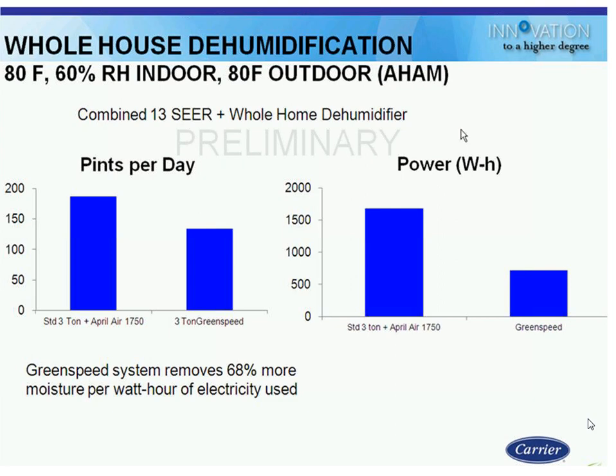This also gives you an idea on how much of a dehumidifier this guy can be. This is a 3-ton unit. On the left side, it's how much moisture is being removed. That first blue bar, where it says standard 3-ton plus AprilAire 1750, is saying it's removing 175 pints per day of moisture out of somebody's house by having both their 3-ton air conditioner and their whole house dehumidifier running at the same time. If I were to put on just one of these 3-ton Carrier Greenspeed or Bryant Extreme heat pumps, I'm going to get, we'll call it, 130 pints per day. I'm going to get almost as much moisture removal as this other system that has a special dehumidifier added.